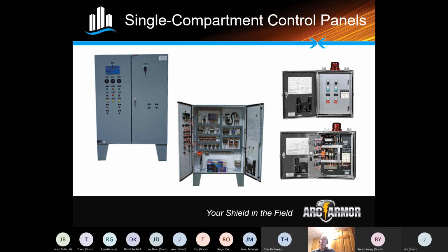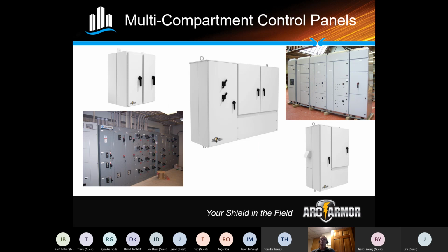304 is more cost friendly than 316, but 316 is also a more pure stainless steel and will resist rusting and pitting more than 304. 304 has a little more irregularity in the steel and could cause some rusting issues, especially in high salt areas. So that's single compartment, and then you can get into what they call multi-compartment. The motor control center lineup over here is considered multi-compartment, multi-buckets.